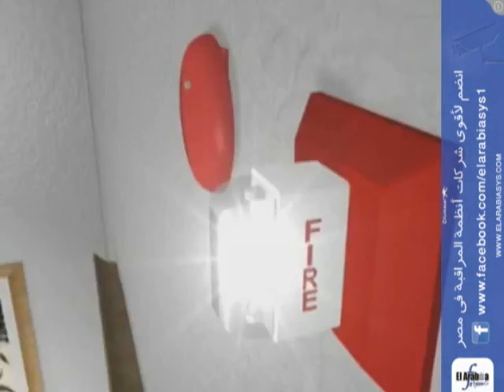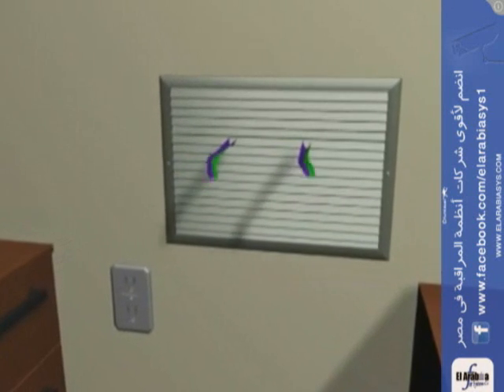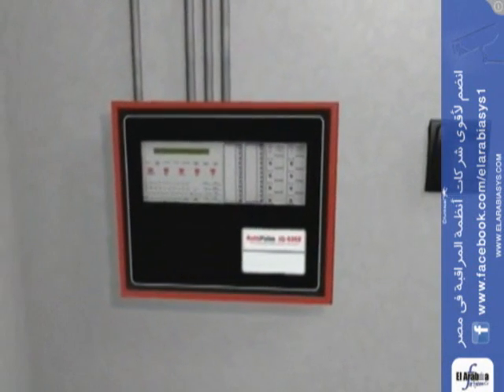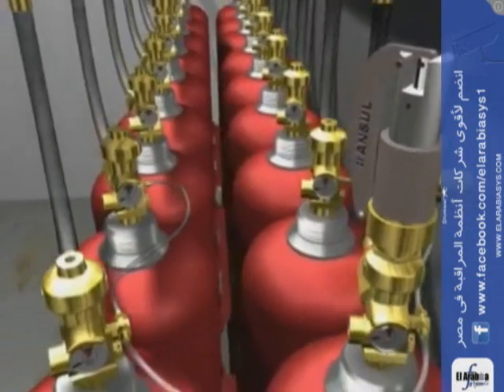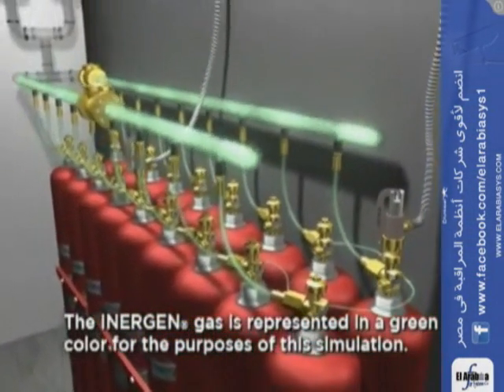Audio and visual alarms are started, and the ventilation systems are closed off. After the prescribed time-delayed period, the autopulse control unit energizes the electric actuator on the Inergen cylinder valve. The cylinder valve opens, allowing the Inergen agent to discharge from the storage cylinders.